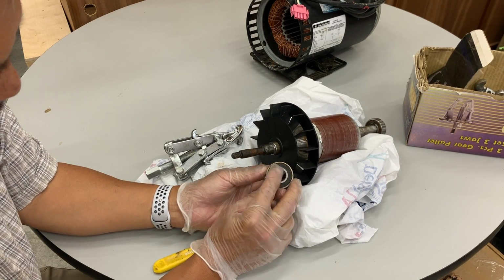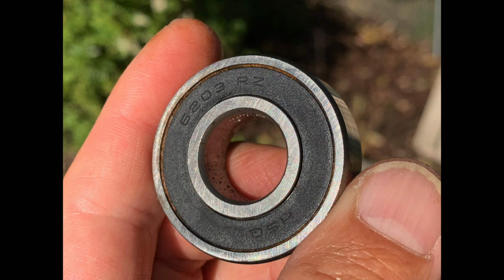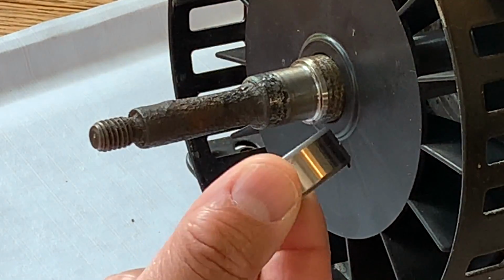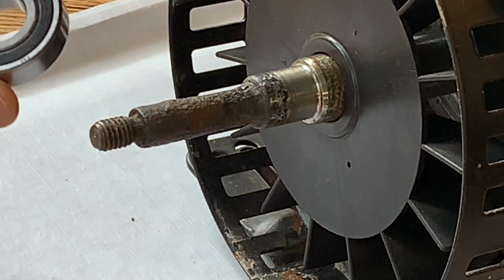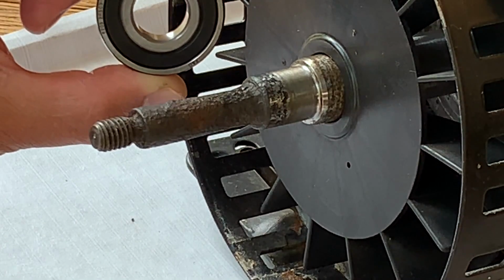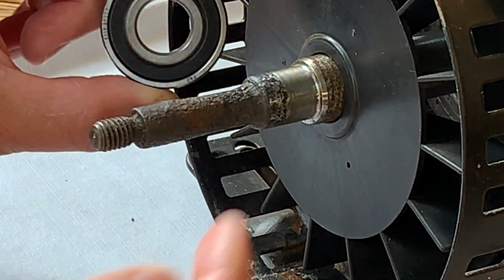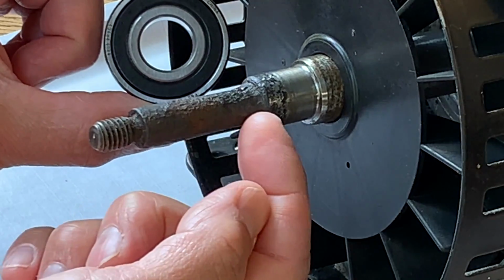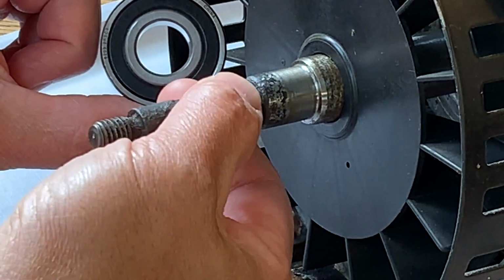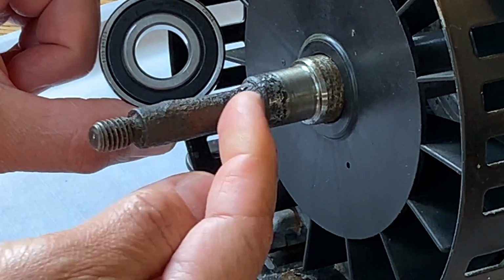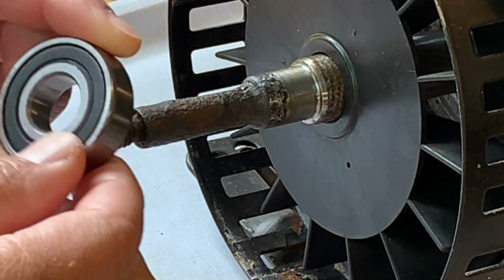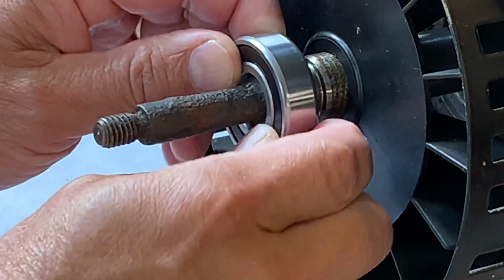Looks like there's some lettering on the inside here. This was a 6203-RZ ball bearing. I was able to locate one and purchase it through eBay for $7 including shipping. We've got the old bearing off. We've ordered a new bearing which just arrived. It's just a matter of replacing the old one with the new one. We can see that the shaft has got a fair bit of corrosion on it here. This may be the last time we can rebuild this particular motor, but we'll see what kind of mileage we get out of it. It just has to go right over the top.